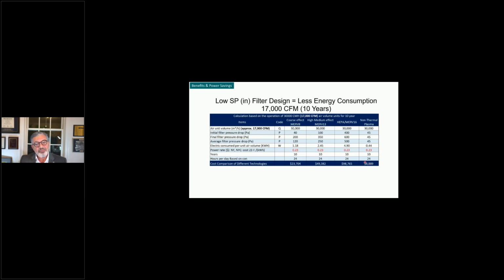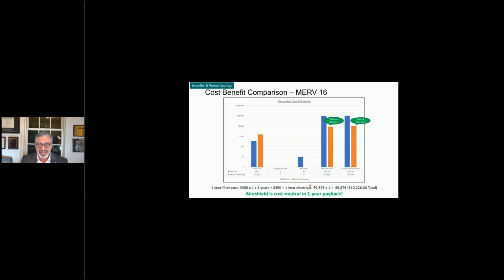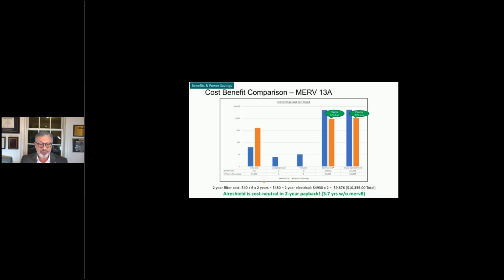Why is this important? Because the payback is less than one year. Even if you only had a MERV 13 filter that you now use as a MERV 8, the payback is anywhere between 2 to 3.7 years. So with these types of technologies, you can agglomerate particles and then reduce the MERV level of filtration you have, but still achieve the higher level.